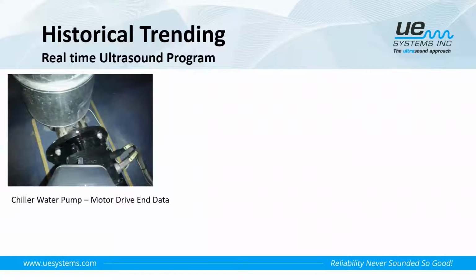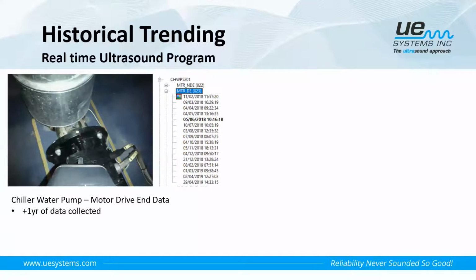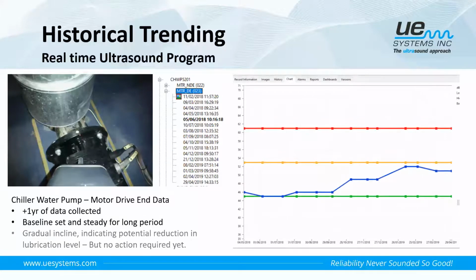So with historical trending, I want to share with you now some examples of a real-time historical trending ultrasound program from a user that uses this technology. One of these is a chiller water pump, looking at a motor drive end bearing. We have over 1 year's worth of data points collected. We can see from the historical chart that the baseline was set and was steady for a long period of time. But then, over a shorter period of time, we start to see a steady climb in the decibel value. We have not quite hit a low alarm level yet. This shows me that the bearing is getting closer to requiring some lubrication, because the level of lubrication is starting to reduce and the friction is starting to increase. So it gives us an indication that something's coming along, and we might need to do something soon.